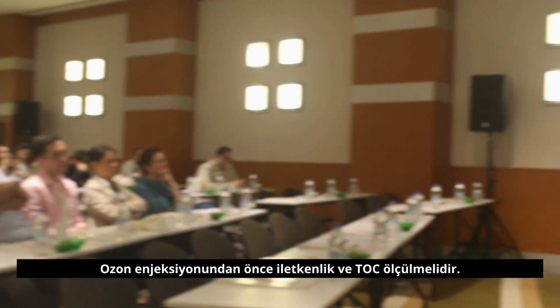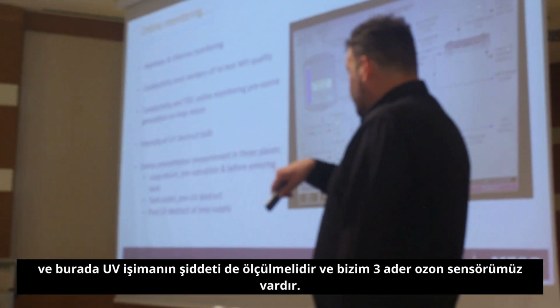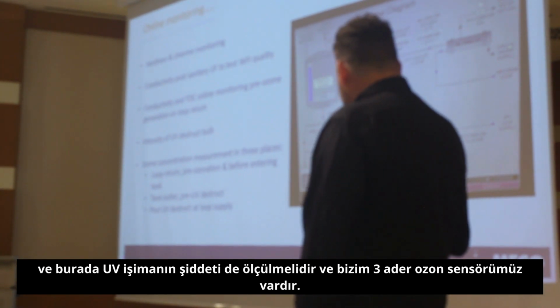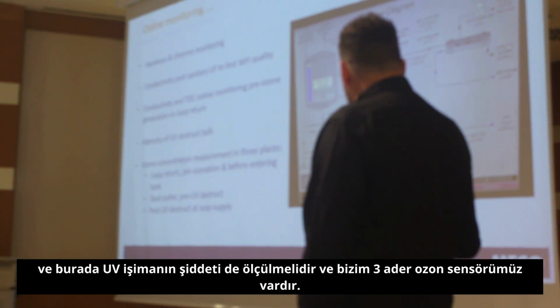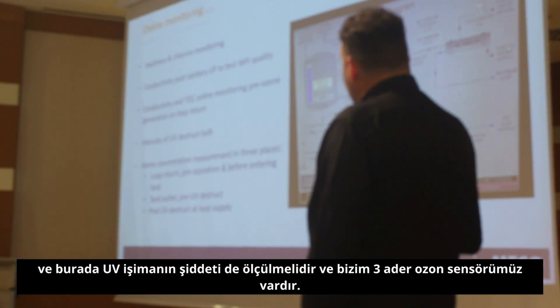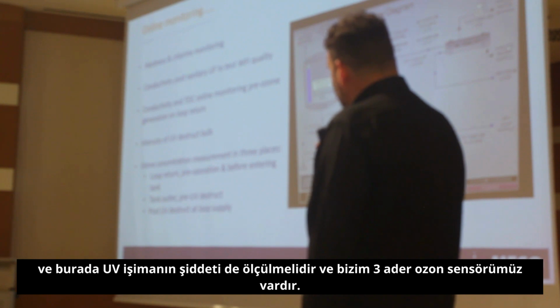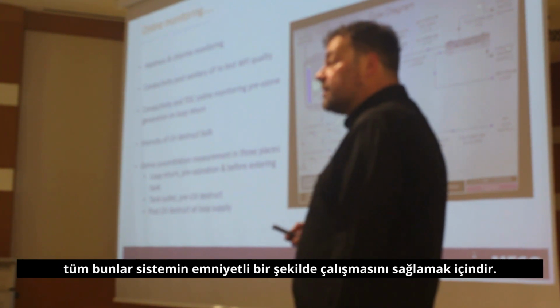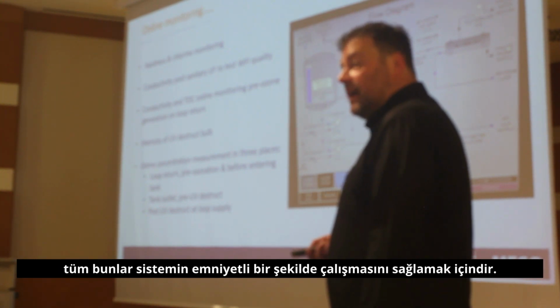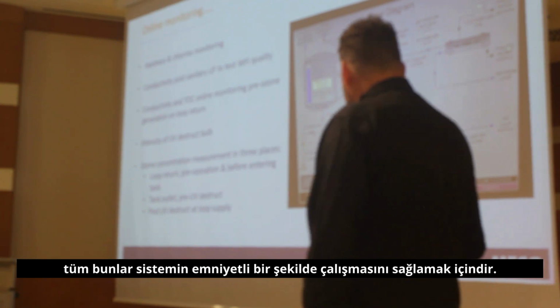Conductivity and TOC are monitored before the ozone injection at the loop return. We also monitor the intensity of the UV light here. And we have 3 ozone sensors in the system that ensure it is operating safely and to quality expectations.